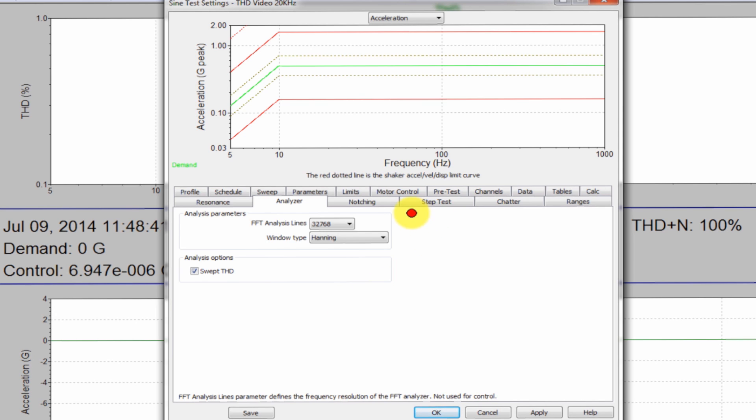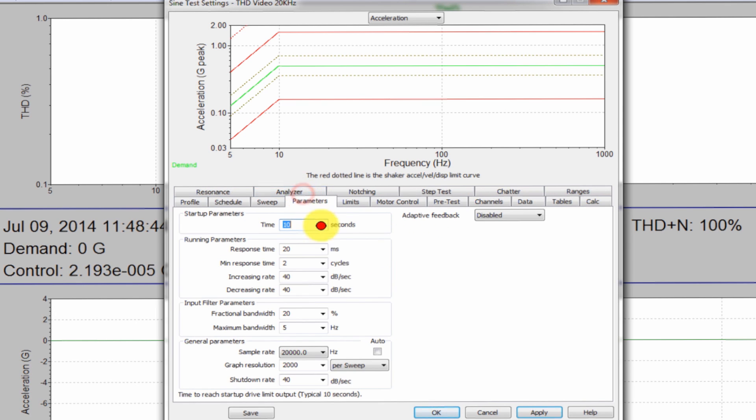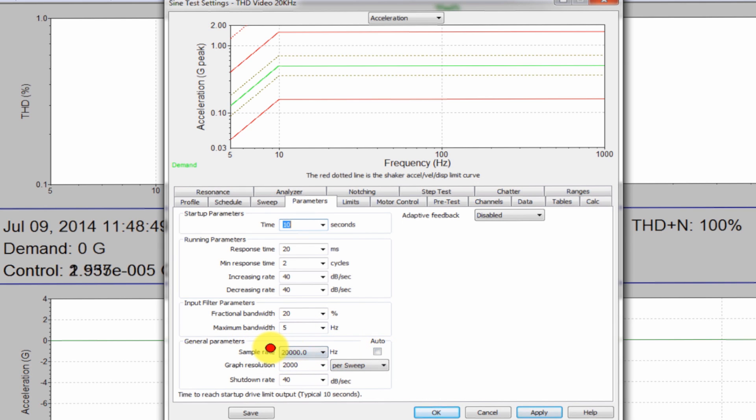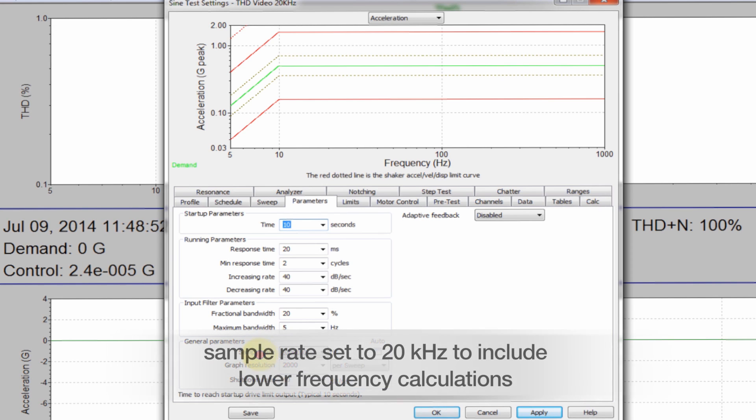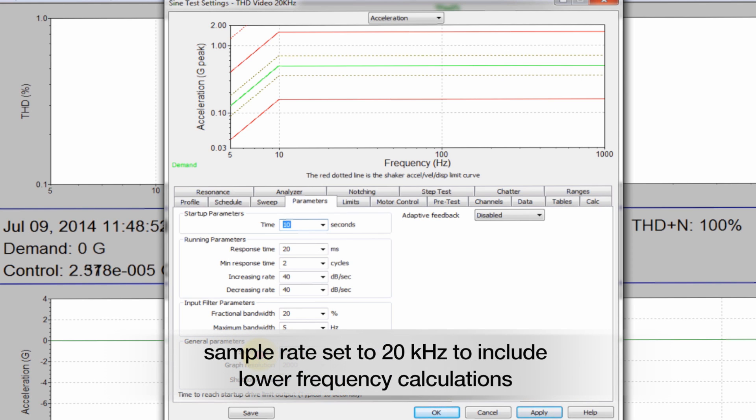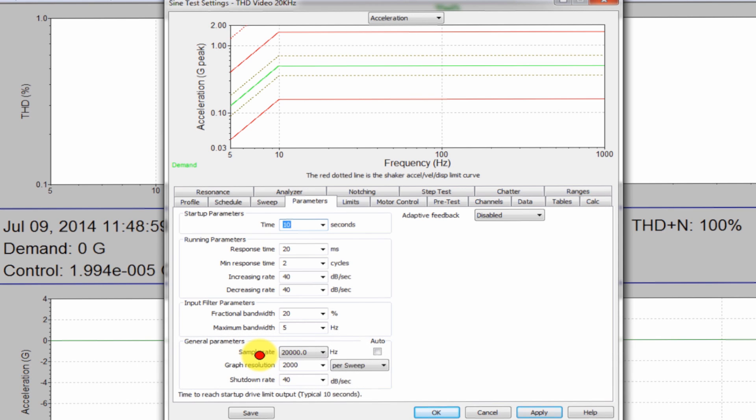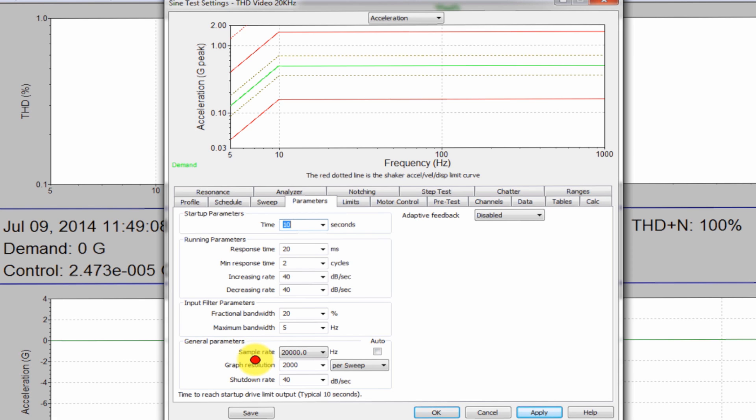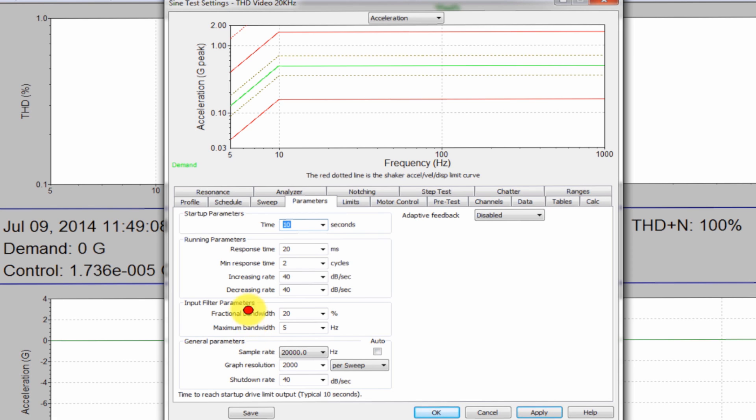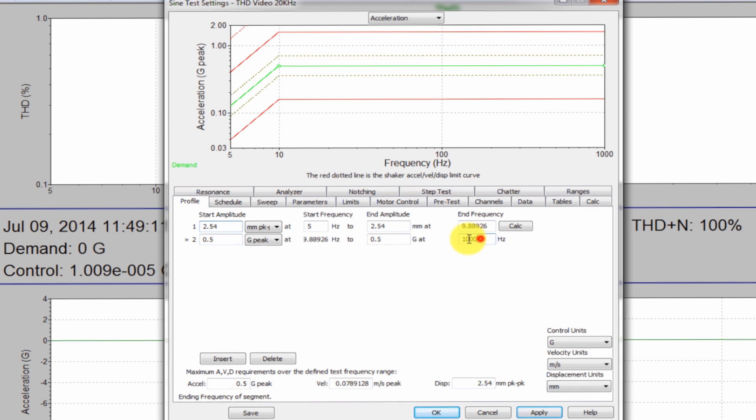On the parameters tab, I've lowered my sample rate. Normally it's set to auto and it's set to about 65 kilohertz. But in this case, I've dropped it down to 20 kilohertz. And the reason for that is at the low frequency, I wanted to be able to calculate starting at 5 hertz. And the only way to do that was to lower the sample rate. The reason that I stopped at 1000 hertz in my actual profile was because above 1000 hertz, I don't have good control at 20 kilohertz.